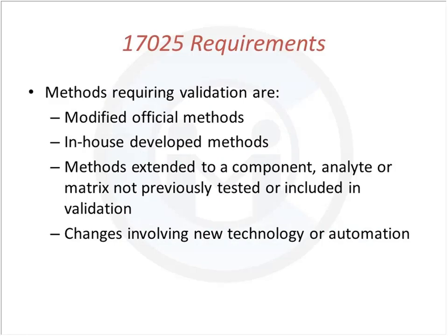ISO 17025 states that methods requiring validation include any newly developed methods — including in-house development — so if you're starting a method from scratch you have to validate its performance and look at the characteristics we discussed. If you modify an official method in any way, you have to validate that change. However, you don't have to validate every single performance characteristic — only the essential ones that could be impacted by the modification.